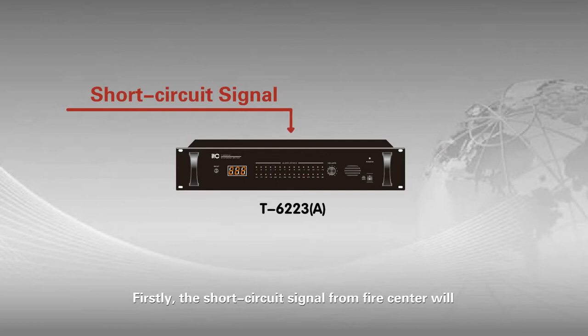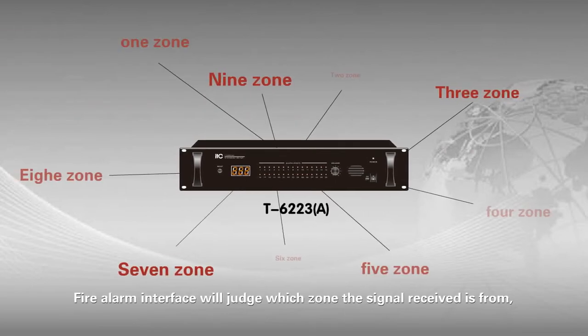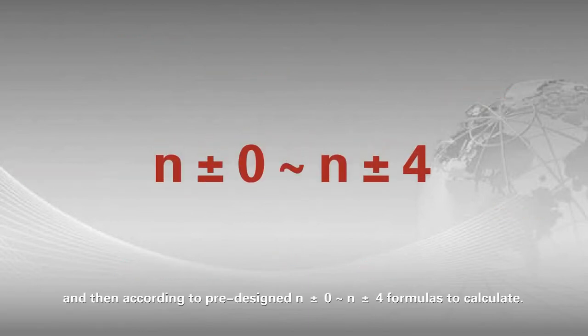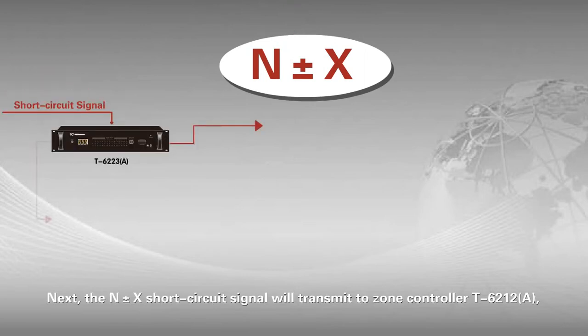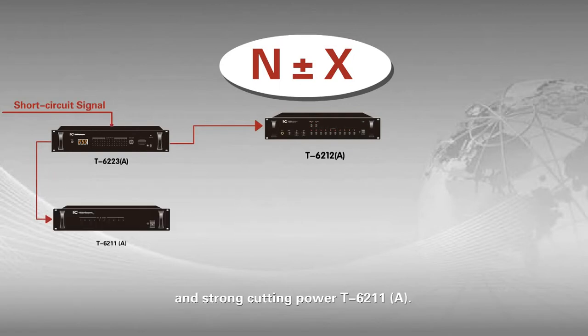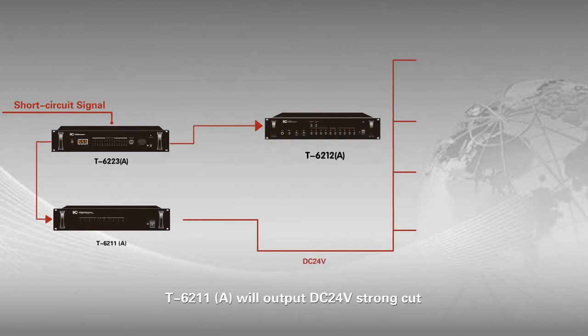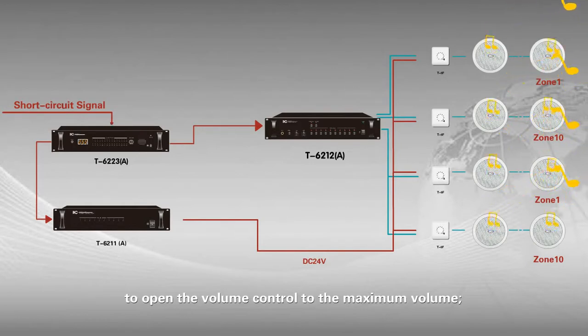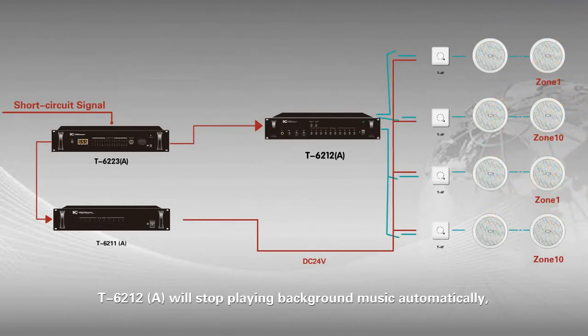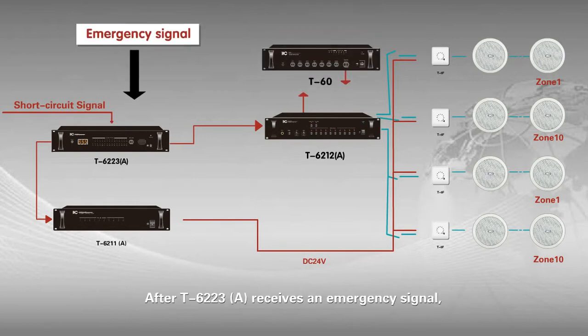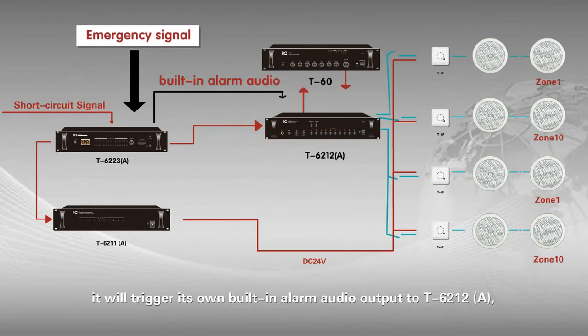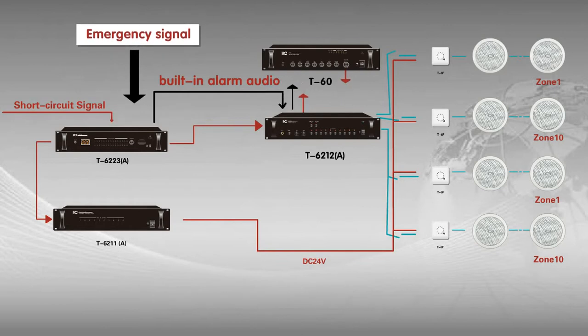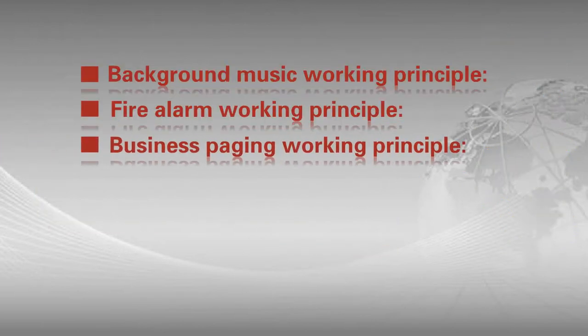Fire alarm working principle. The short-circuit signal from the fire center accesses fire alarm interface T6223A. The interface judges which zone the signal is from, then calculates according to the pre-designed N±0 to N±4 formulas. The N±X short-circuit signal transmits to zone controller T6212A and strong-cut power T6211A. T6211A outputs DC 24V to open the volume control to maximum. T6212A stops background music and switches to the fire paging amplifier circuit. T6223A triggers its built-in alarm audio output to T6212A, which outputs to the fire paging amplifier so the corresponding zones broadcast emergency voice.